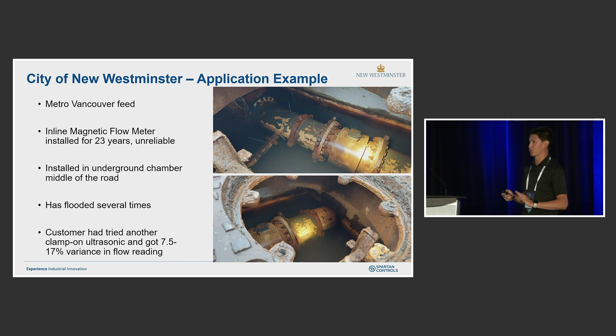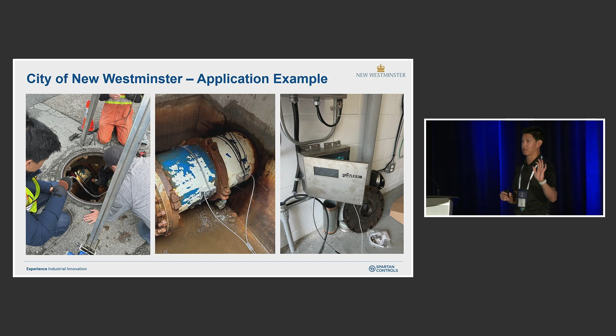We essentially installed the transducers on the side of the pipe, and we had a decent amount of straight piping. Then we wired up the transmitter box about 50 feet away, and we were able to get a pretty good reading out of it.